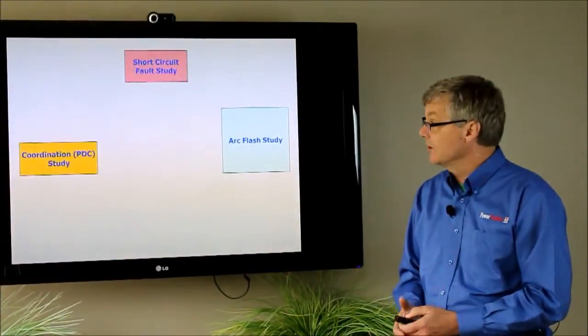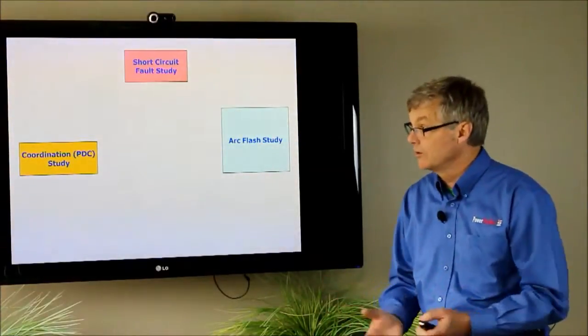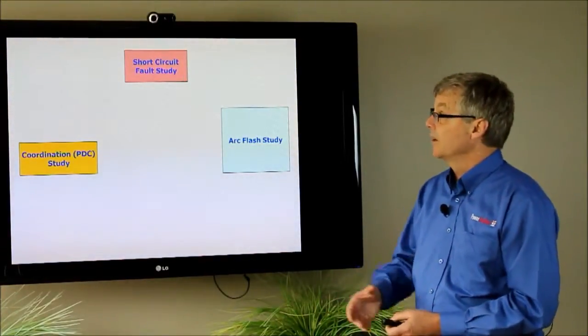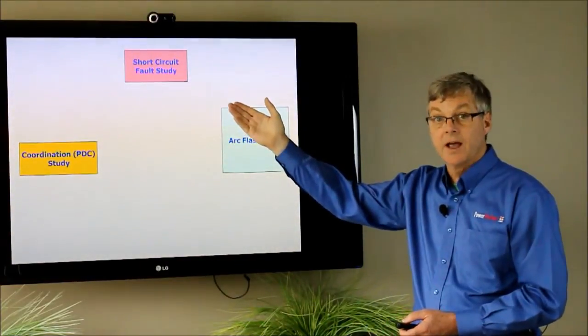Well to do an arc flash study there's two other types of studies you must do before you do the arc flash study and what is called a short circuit study where we will calculate the short circuit current at each piece of equipment in the electrical distribution system.